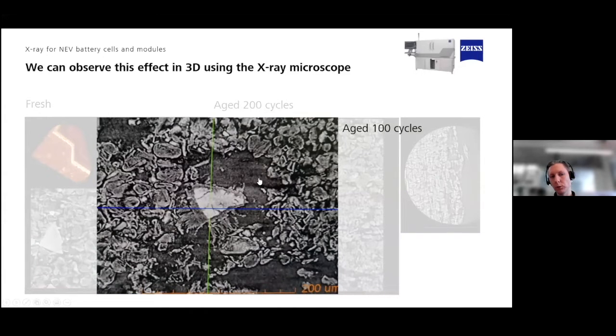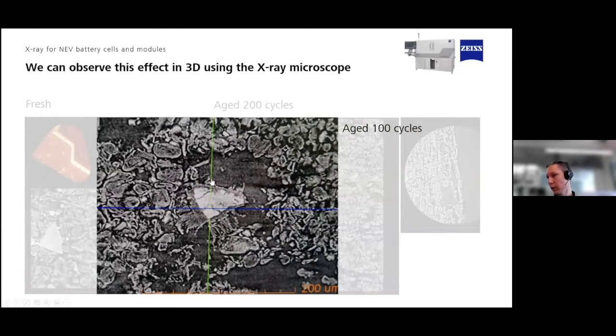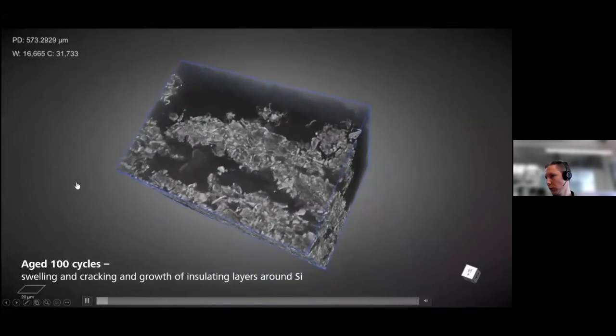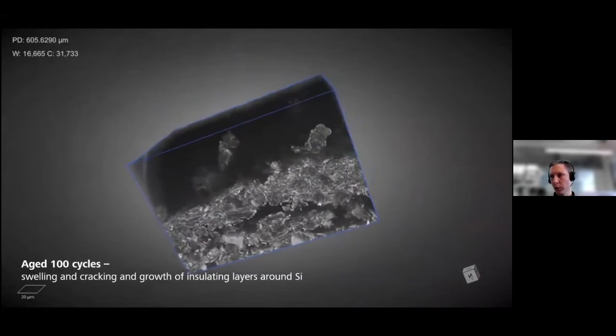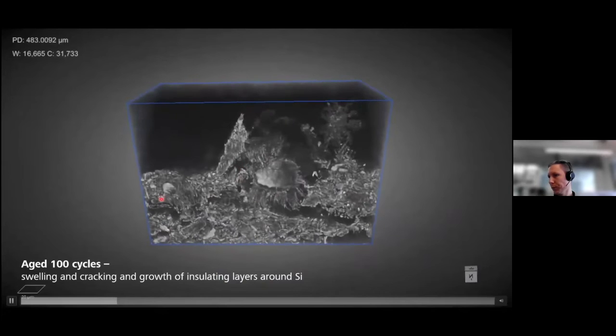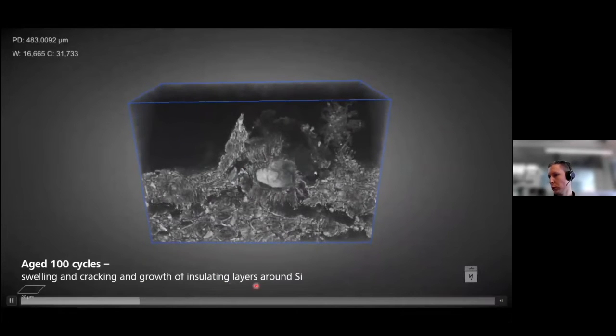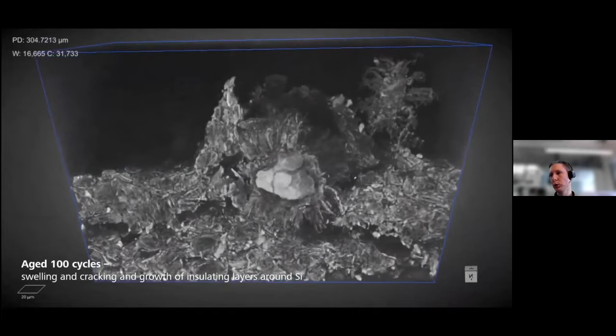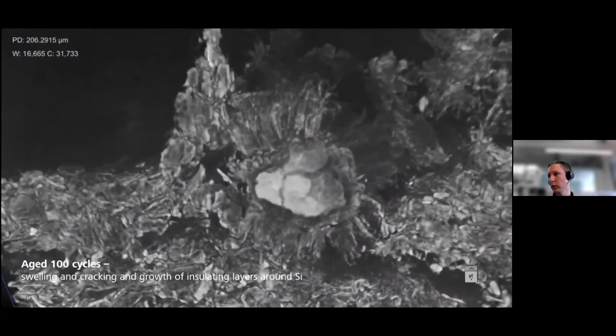Going back to another sample, if you want to know what happened and make an X-ray scan after 100 cycles, you can see what happens with a silicon particle. You can also do something like that using scanning electron microscope, but then you cannot look at the same region of the sample. Here's a short video showing what happened after 100 aging cycles with the silicon — you can see swelling, cracking, and growth of an insulating layer, giving a real understanding of your base materials used for producing battery cells.